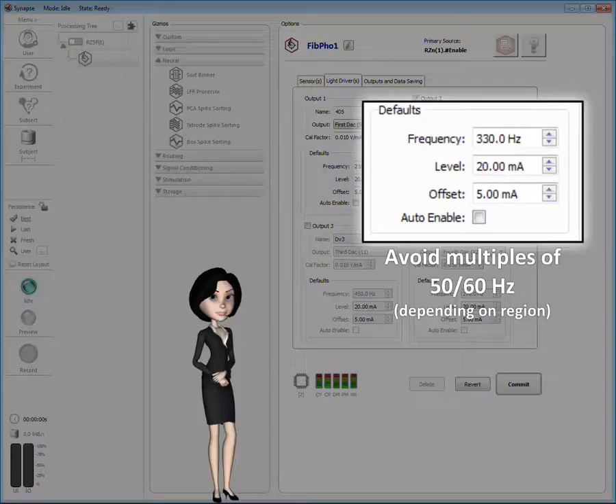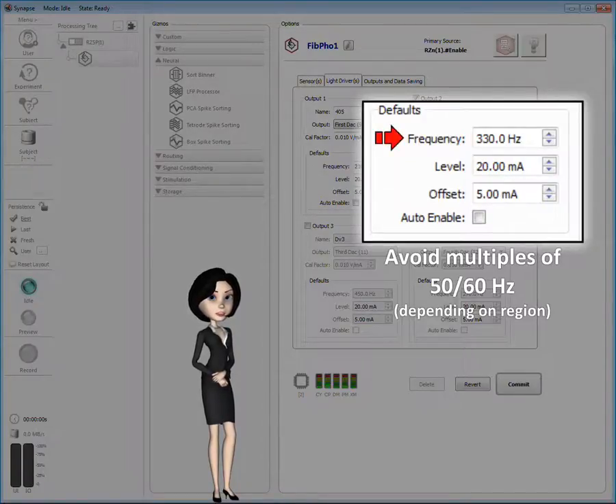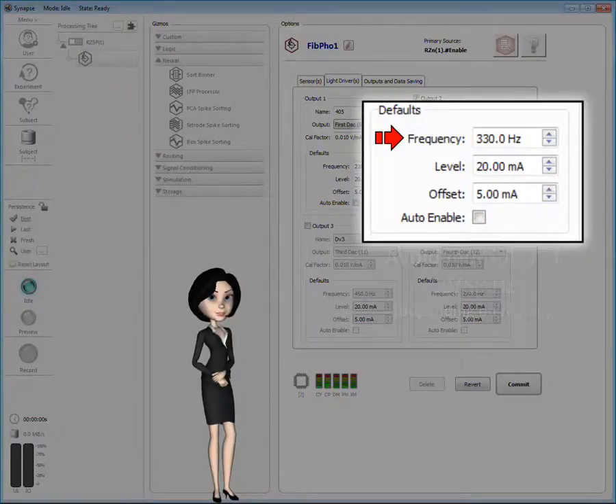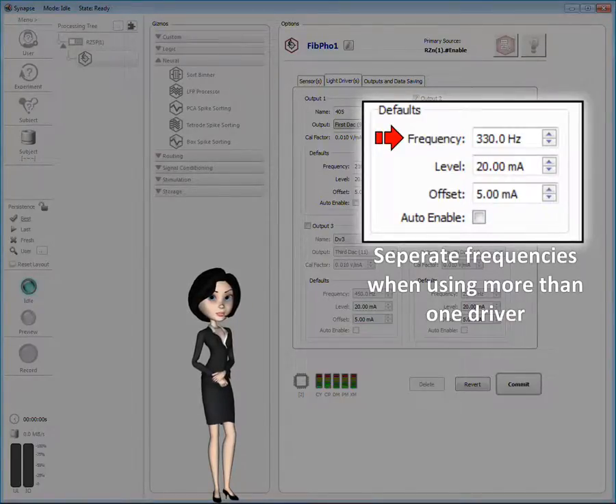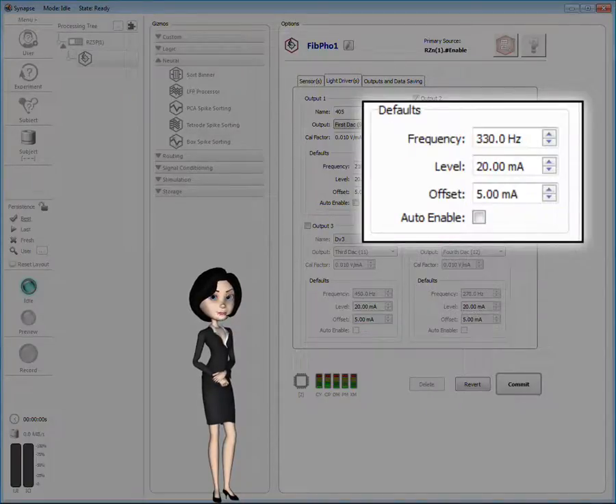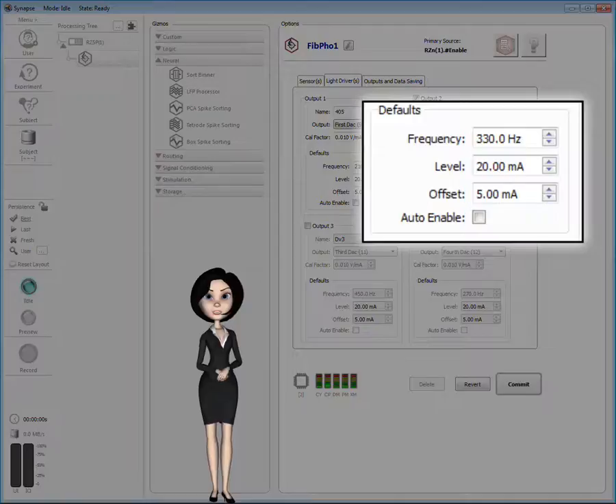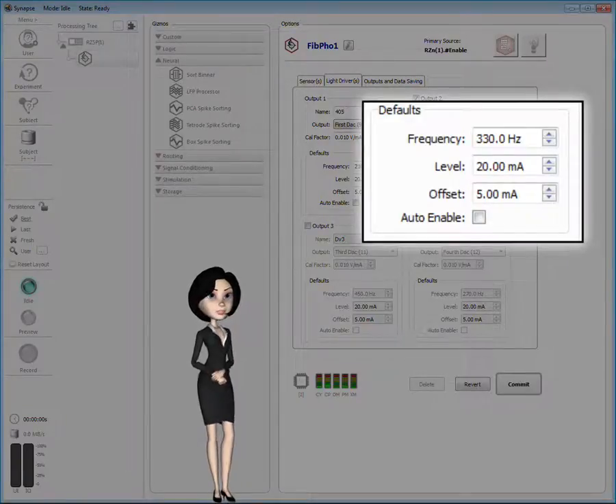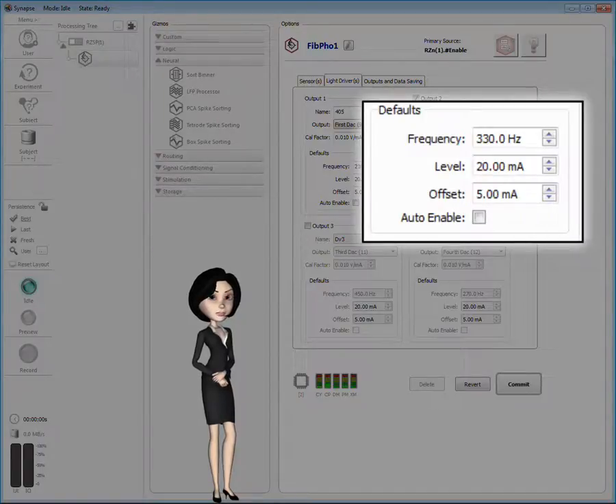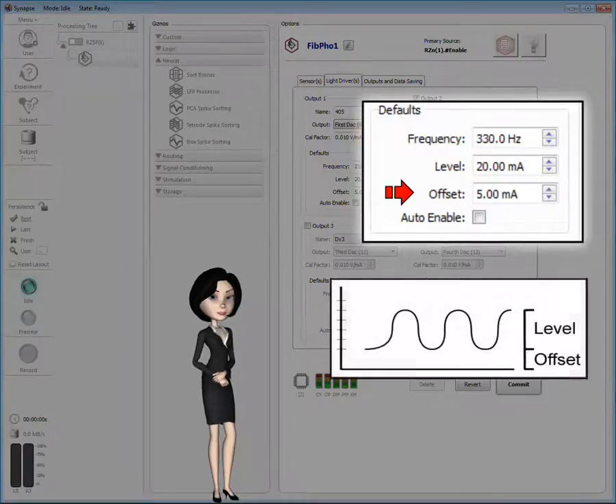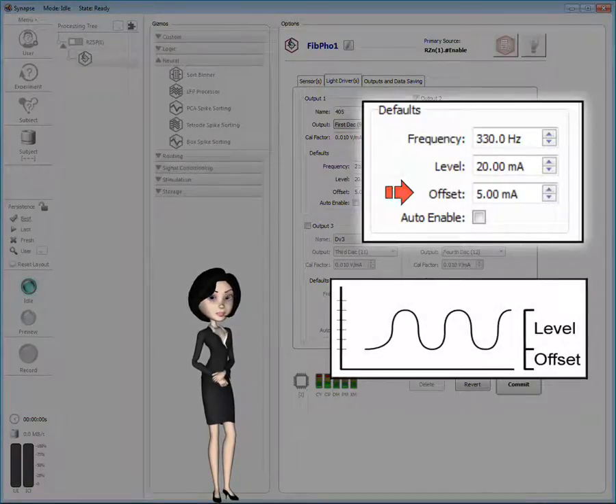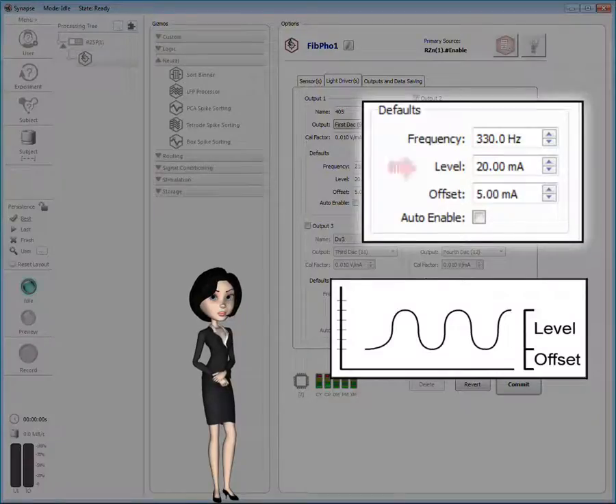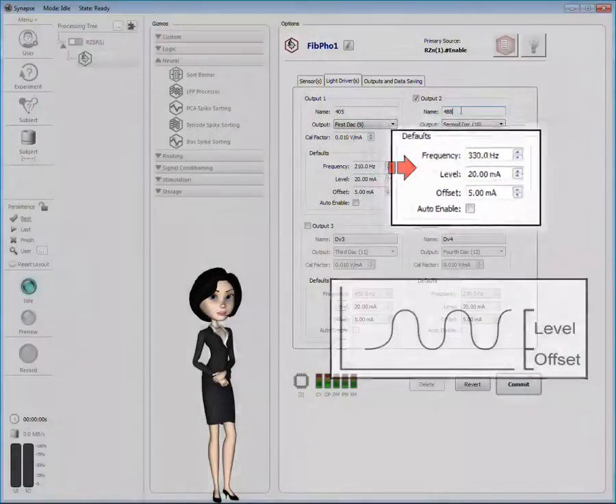Whilst avoiding 50 or 60 Hz and their multiples, you can use whatever modulation frequency you prefer. However, if you are using more than one driver, make sure the carrier frequencies are clearly separate and distinct. This will ensure the best results when the response signal is demodulated. The level and the offset work together to tweak the linear range of your light driver hardware. The offset accounts for the minimum power the driver requires to produce the desired light from your light source. The level determines the light intensity within the driver's usable range.